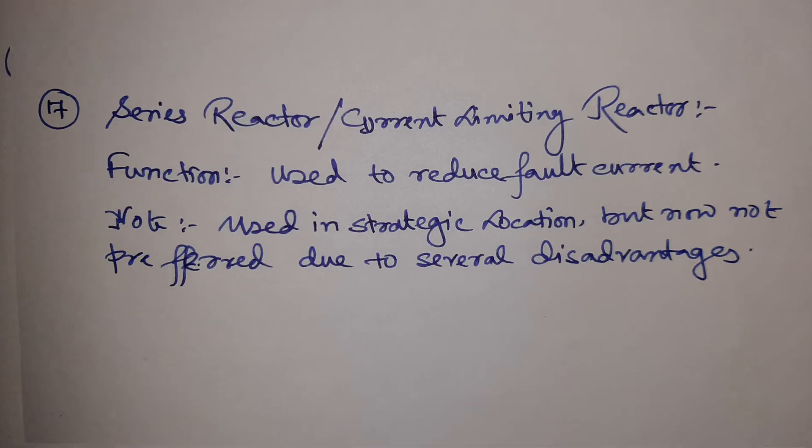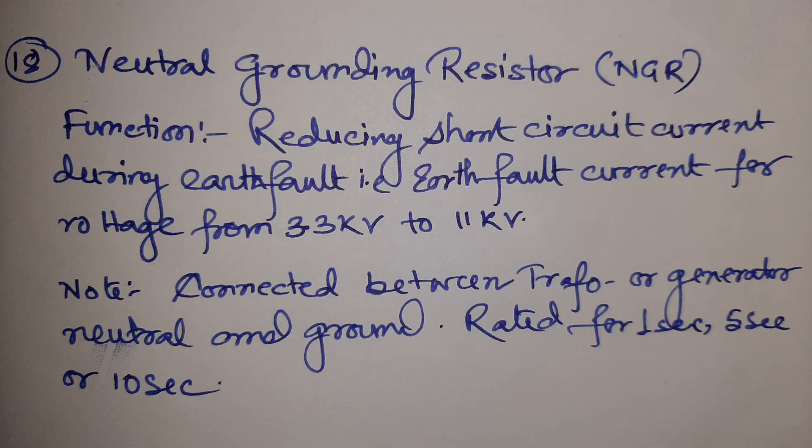Our next equipment is the neutral grounding resistor or NGR, also known as NER or neutral earthing resistor. Its function is to limit the earth fault current, and it is used in voltage ranges from 3.3 kV to 11 kV. I have already dedicated a video on NGR and its calculation, so you can check that. It is connected between the transformer or generator neutral and ground. Its ratings are for one second, five seconds, or ten seconds — meaning it restricts the earth fault current for that duration. For example, an NGR designed to restrict earth fault current at 400 amperes would be rated 400 amperes for one, five, or ten seconds.